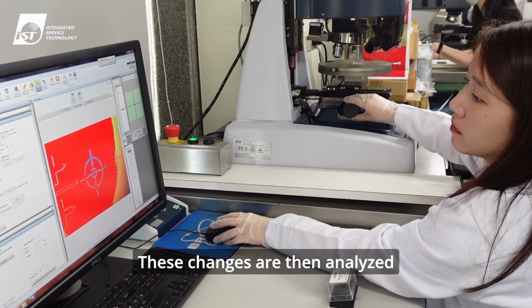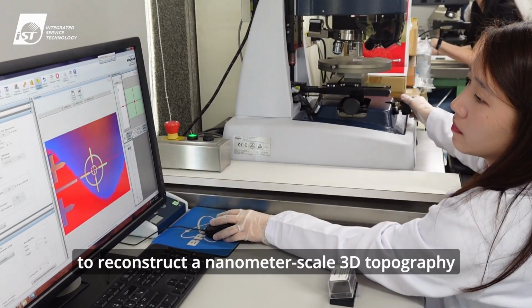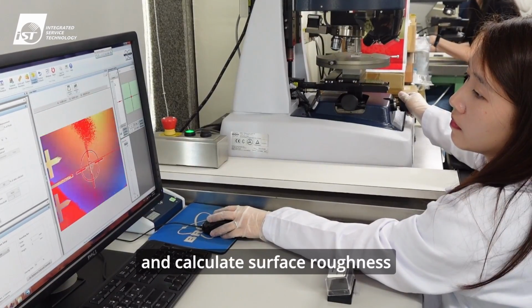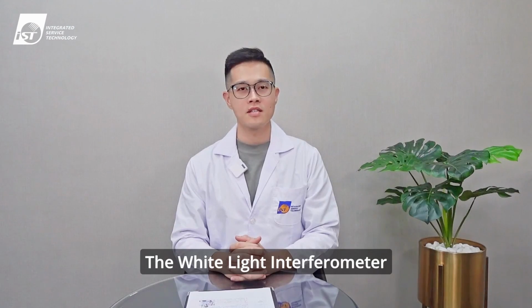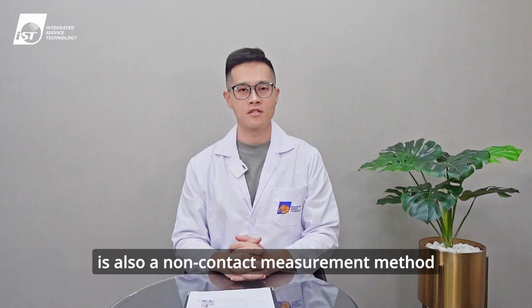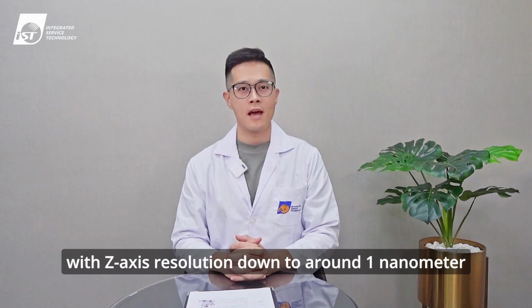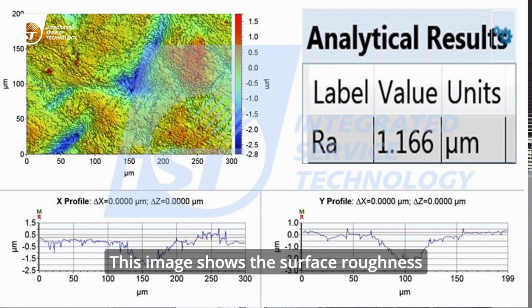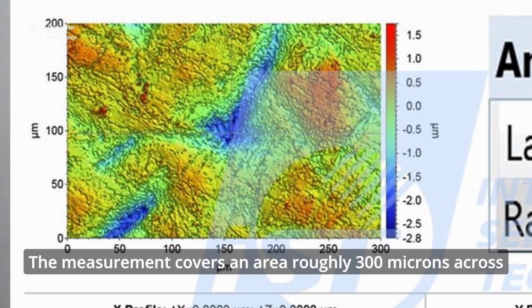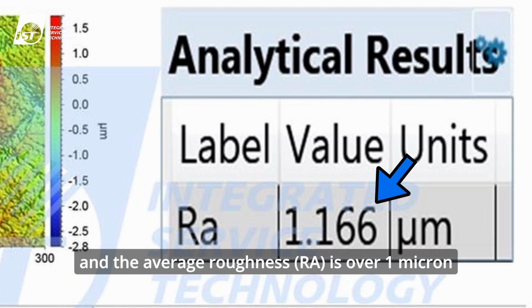These changes are then analyzed to reconstruct a nanometer scale 3D topography and calculate surface roughness. The white light interferometer is also a non-contact measurement method, with Z-axis resolution down to around 1 nanometer. This image shows the surface roughness of a metal sample after acid cleaning. The measurement covers an area roughly 300 microns across, and the average roughness is over 1 micron.